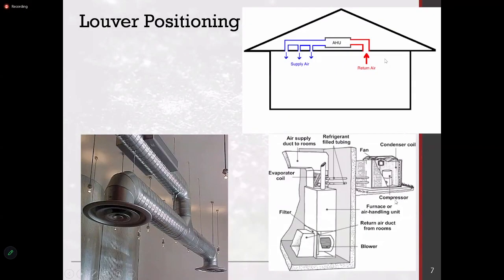generally the cold air is actually at the bottom of the room, because it's heavy, and hot air is on top. So in this type of circulation, it will not do the job properly, because you're sucking air from the bottom, you're sucking the cold air and making it further cold and bringing it. So this type of air circulation is not that recommended, but this is a better arrangement where you absorb from the top, and actually you can even supply to the top. So that is fine.